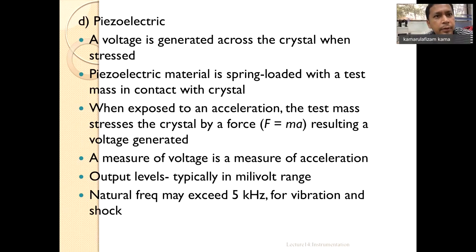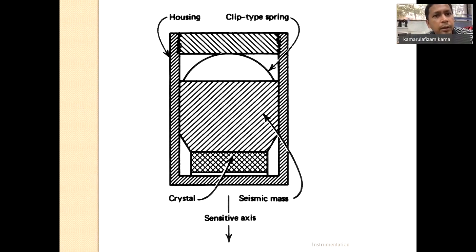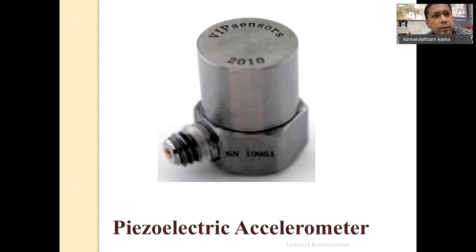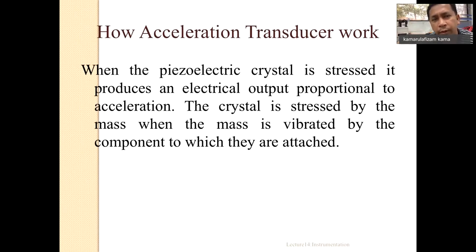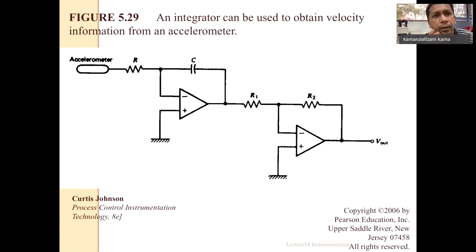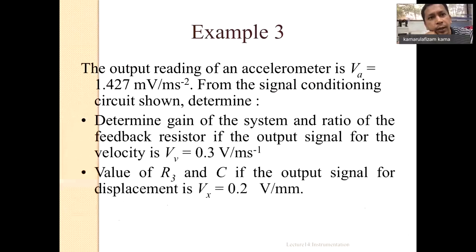The piezoelectric type of accelerometer is based on a crystal. When it is stressed or pushed by the mass of the accelerometer, it produces a voltage and current. When using a piezoelectric accelerometer, you need a signal conditioner, which acts as an integrator. This circuit is used as the signal conditioner for the accelerometer.